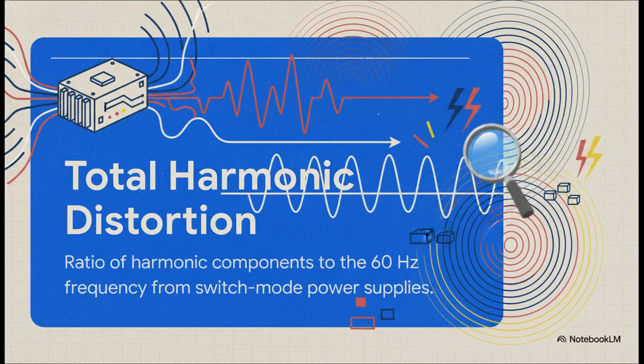Down in the projection room, we encounter an entirely different electrical beast. Modern commercial digital and laser projectors don't draw power in a smooth, continuous wave like an old-school light bulb. Because they use solid-state switch-mode power supplies, they sip power in these harsh, highly non-sinusoidal pulses. This creates what's called Total Harmonic Distortion, or THD. Essentially, the equipment is injecting high-frequency electrical noise right back into the building's power grid.